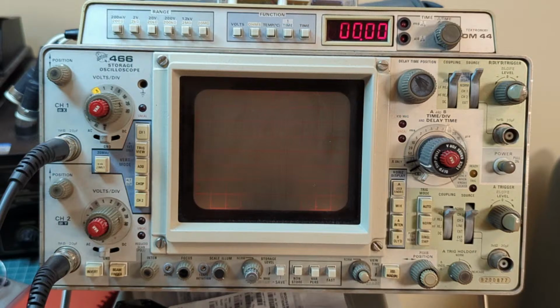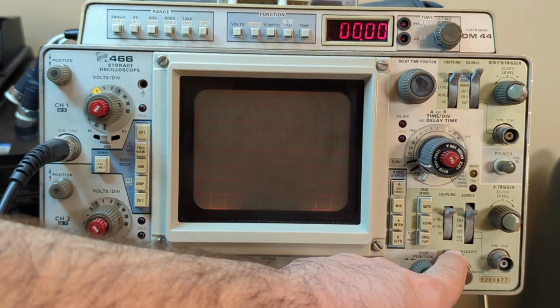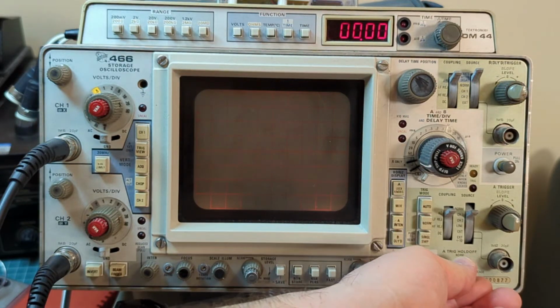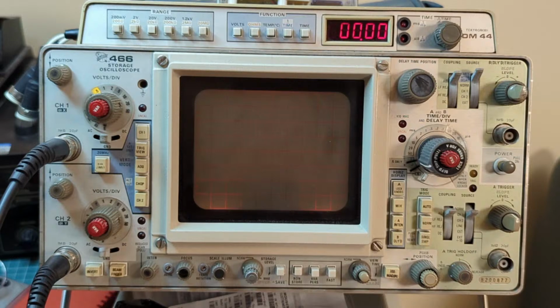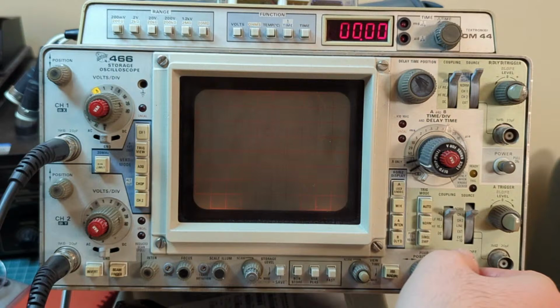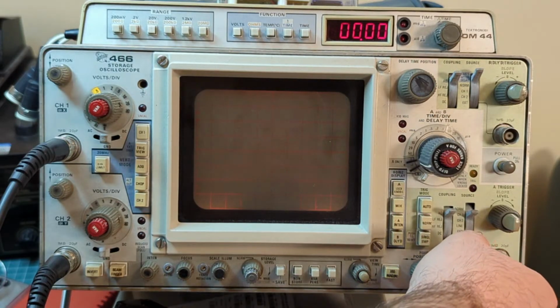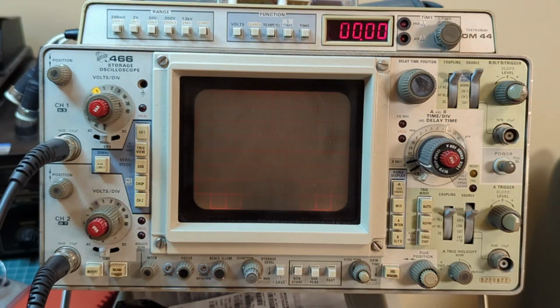And also in some cases the display can get messed up when the trigger event occurs, and maybe you don't want to trigger on every single edge of a signal or something like this, especially if you're looking at a video signal or something like that. And this is where the trigger hold off comes in handy. So you can adjust the hold off manually in some cases, which once again adjusts the break between two sweeps. So if nothing else works, this is worth trying out, and sometimes this makes the display a lot cleaner.